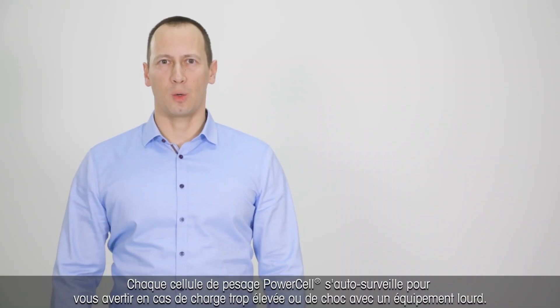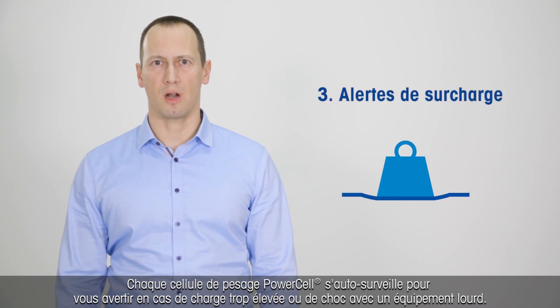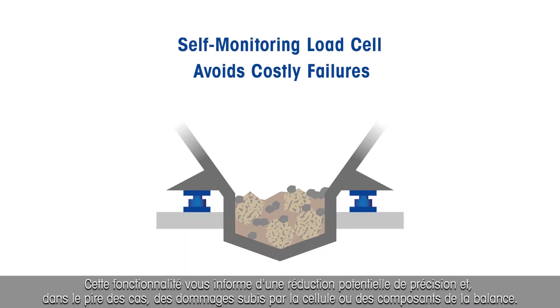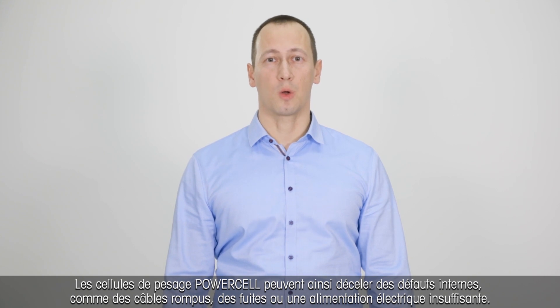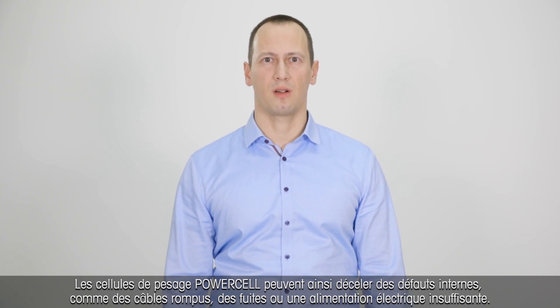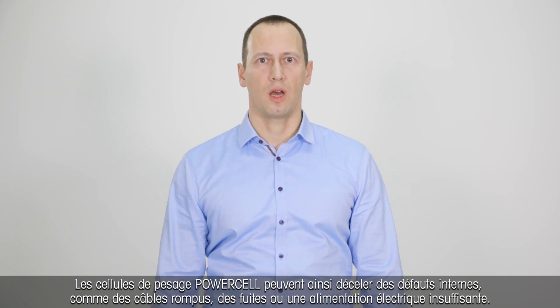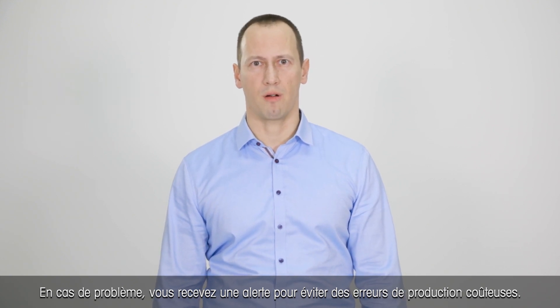Each PowerCell load cell also self-monitors to tell you when the load is too heavy or has had a run-in with heavy equipment. This self-monitoring tells you about potential reduction in accuracy and, in the worst case, damage of the load cell or components within the scale. PowerCell load cells constantly monitor themselves for internal defects such as broken wires, leakage, and insufficient voltage supply. If anything is amiss, you will receive an alarm to prevent costly production errors.